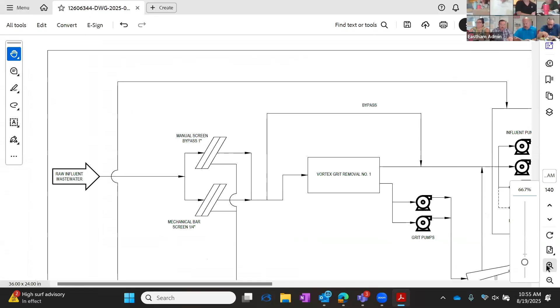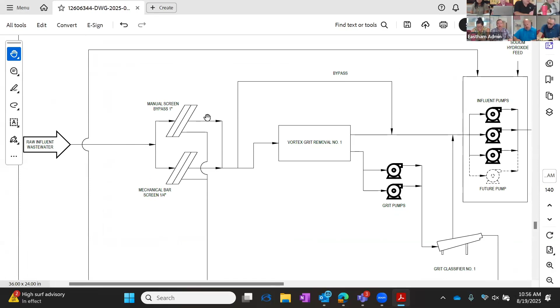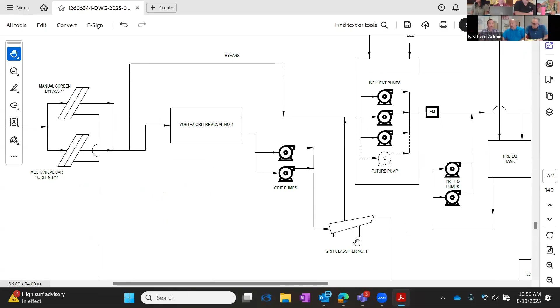Starting out here, we're going to have the influent wastewater coming in, with an influent composite sampler pulling a sample from the wastewater prior to any recycles inside the plant. It runs through two channels: a manual screen for cleaning, and a mechanically cleaned bar screen with 1/4 inch openings. Downstream from that, it flows into a vortex grit unit, with a bypass around it if you need to take it out of service. Two pumps serve the grit pumps, pulling grit from the vortex grit unit and pumping it through the grit classifier, which dewaters the grit and puts it into a container to be hauled to the transfer station for ultimate disposal.